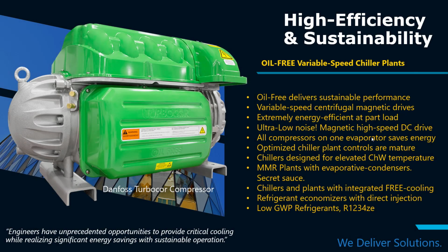Many of you know that I came from the world of Turbocor since its beginnings. Turbocor delivers oil-free, sustainable performance. They are variable speed centrifugal compressors, magnetic drives that achieve very, very low energy usage at part load. They are ultra low noise. The magnetic high-speed DC drive is virtually silent. All compressors are on one evaporator, which conserves energy. Optimized chiller plant controls are very mature now, across multiple chillers and multiple compressors on each evaporator.